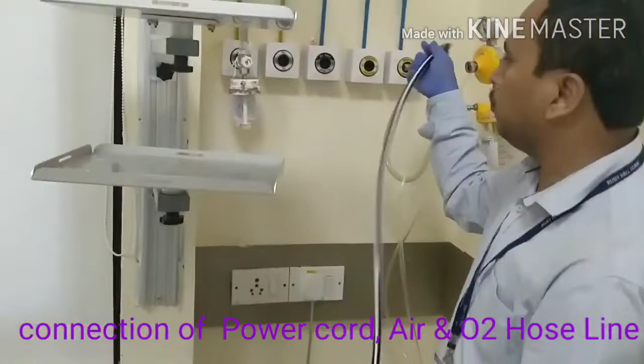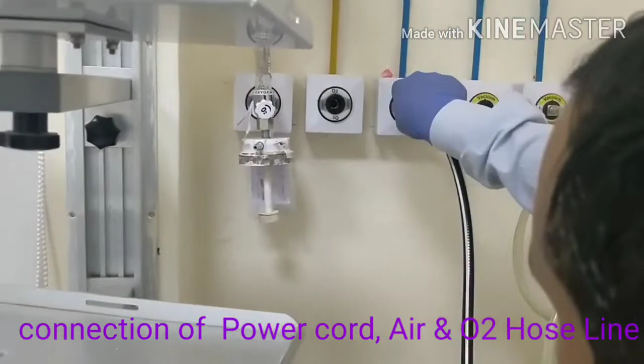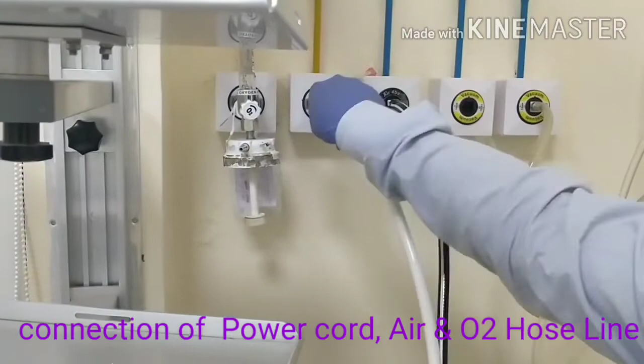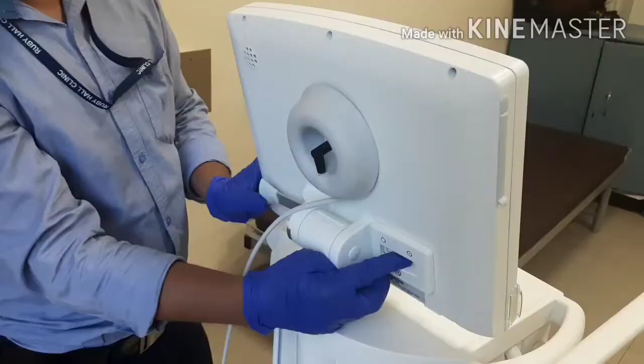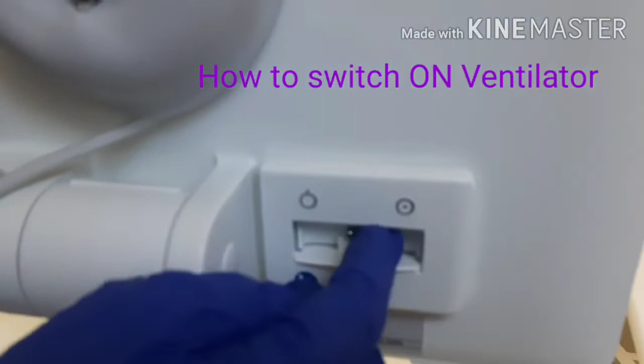We have to connect this air and O2 hose line at the central air and O2 point. So see how to connect it. This is the air supply, just push it, and this is the O2 supply, just push it. This switch turns on the ventilator, so the flap will close for safety purposes. Here the ventilator is switched on.